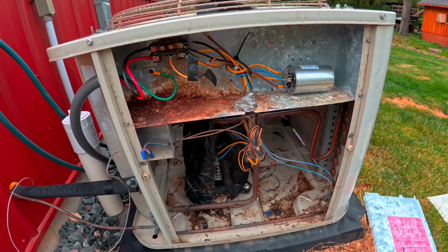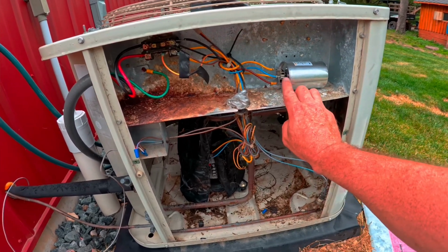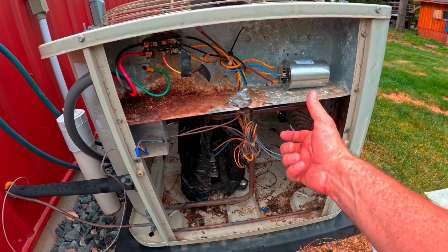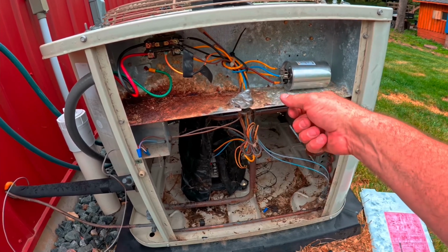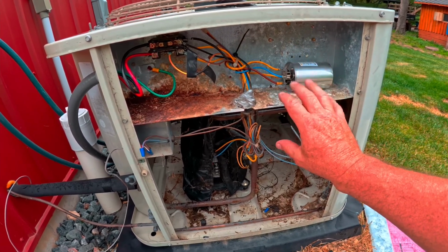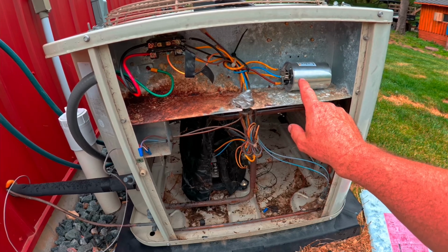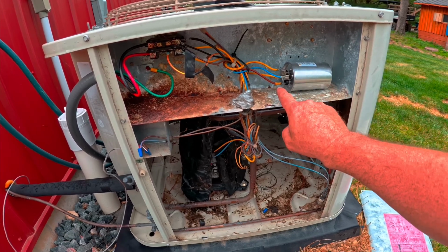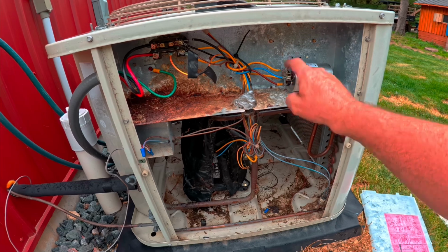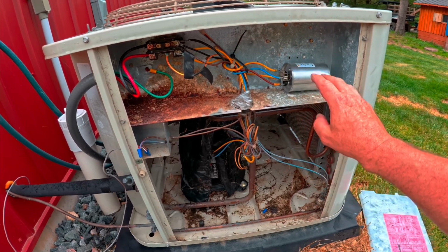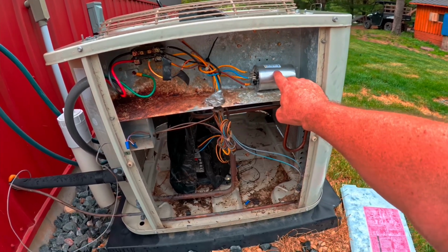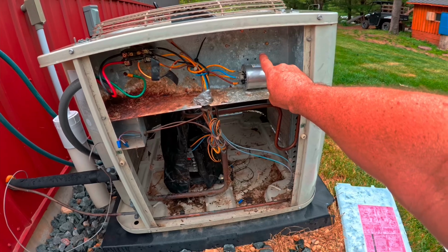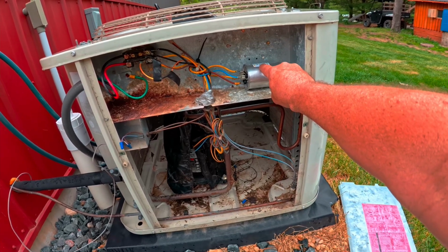And even then, I never suggest grabbing a hold of these wires. I'll take a pair of insulated pliers, pull the wires off one by one, let them hang there nicely. Remember where they go, okay? One's power, one is Herm, which is compressor, and one is fan. Don't mix them up. These are rated. They have ratings on them. You have to replace it with the same rating that it has, okay?